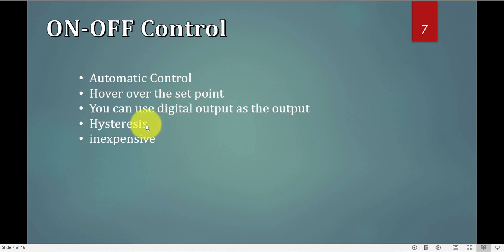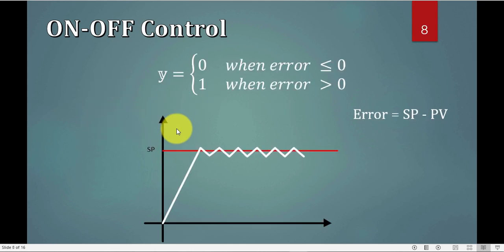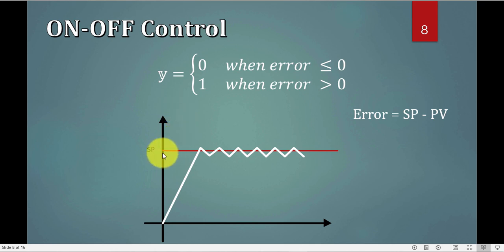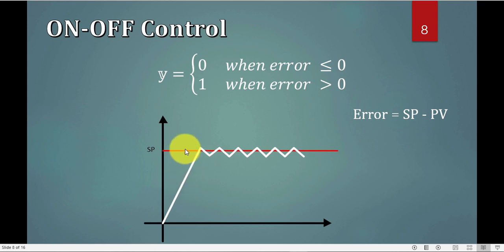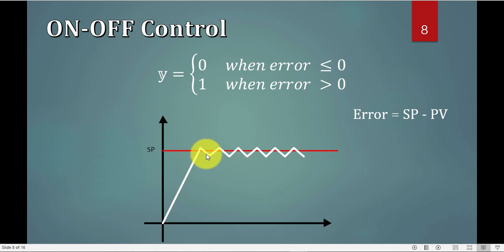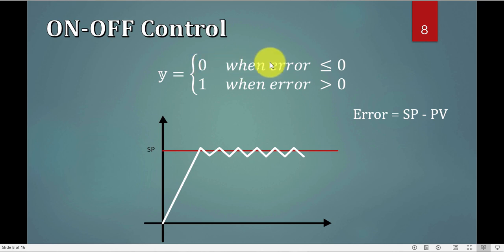You may have to use hysteresis, we'll explain on hysteresis in the next slide. So on-off control, if I want to write the equation for on-off control, it's really very easy. If my PV, which is the white curve, less than the set point, I need the controller to be on, to be one. Once I reach the set point, or go above it, I need to turn off the controller, so it is on-off, on-off, on-off.